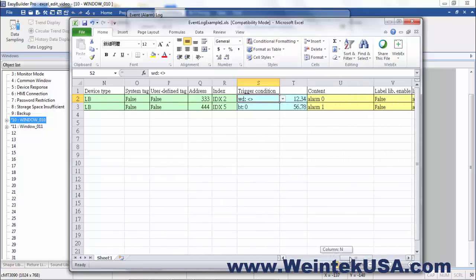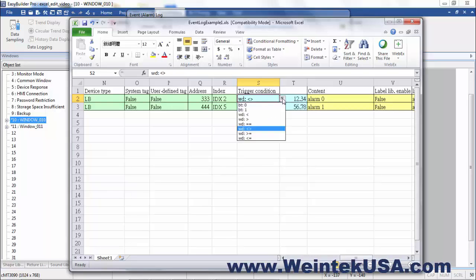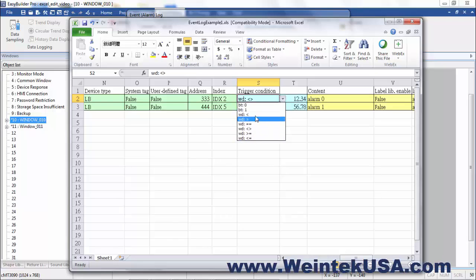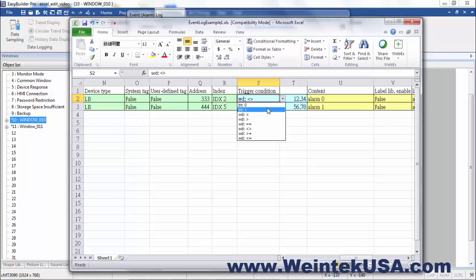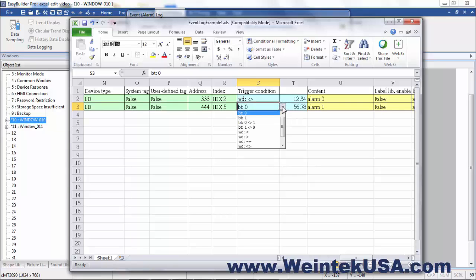Over here in the blue is the trigger condition of the event address. If it were a word, of course, they've got all the different conditions that it could be. Greater and less than, equal to, not equal to, equal or greater, so on and so forth. And then, on the bit conditions, of course, they have off and on. And there should be some more conditions. Yeah, here we go. We've got off, on, and from off to on, or from on to off.